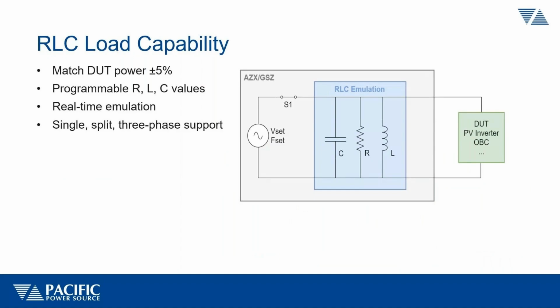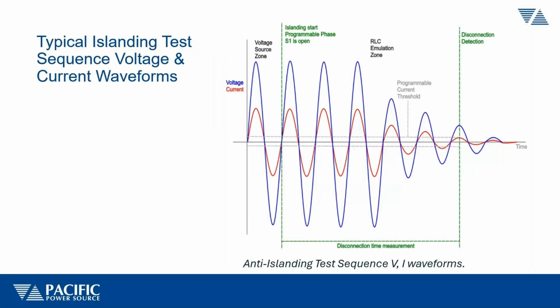If we take a closer look at the load that is in between the grid simulator and the DUT, it obviously has to be able to handle the maximum power level, and it has to be adjustable. The values are not fixed; they may have to be set to different values for different test conditions, and of course, it has to work in real time. What was typically done in the past, as I mentioned, was using RLC load banks that are complex in terms of wiring and adjusting. They're not easily programmable, so it's not a very convenient way, and that's where using electronic load emulation or load simulation can be of significant advantage. We'll see that in a subsequent section.